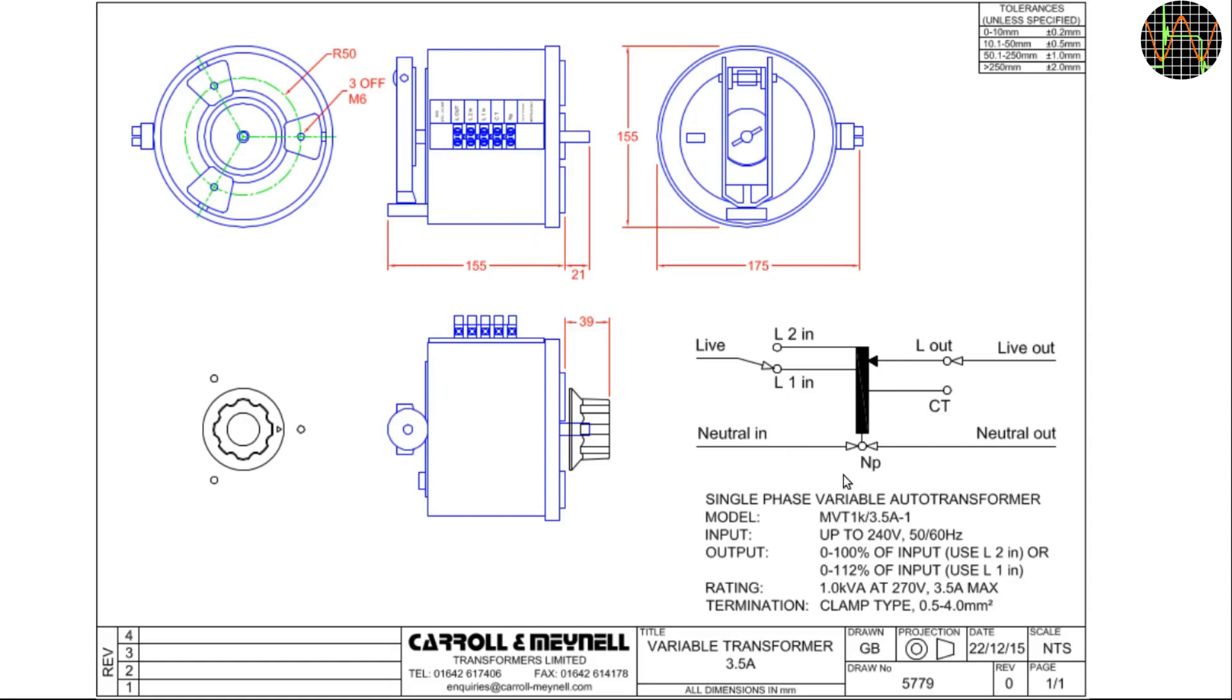The other important bit on this drawing is the wiring diagram here. This transformer has a choice of two input connections for the live wire. If you connect it to L2, which is the very end of the coil, then the output can go as high as the input voltage, which is when the slider basically touches L2. So at an input of 240V, you get 0 to 240V as an output.